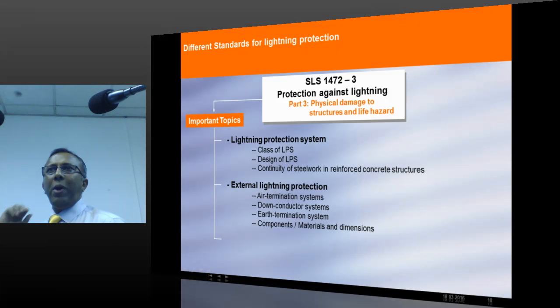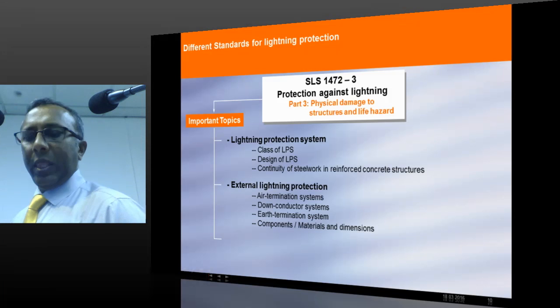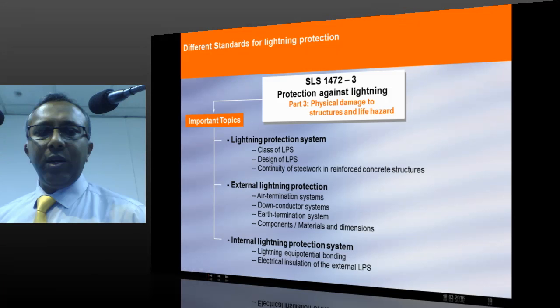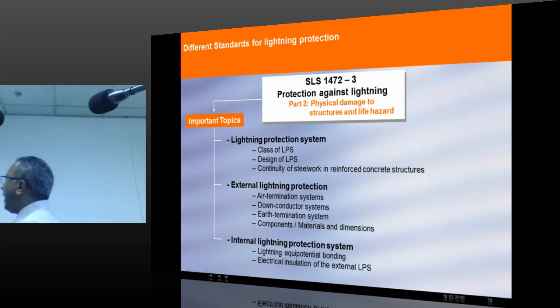Then we go to part number 3. Part number 3 talks about class of LPS and design of LPS. What is class of LPS? The lightning protection system in a particular building is divided into 4 classes: class 1, 2, 3, 4, or lightning protection level 1, 2, 3, 4. The strongest one is level 1 and the lowest one is level 4.